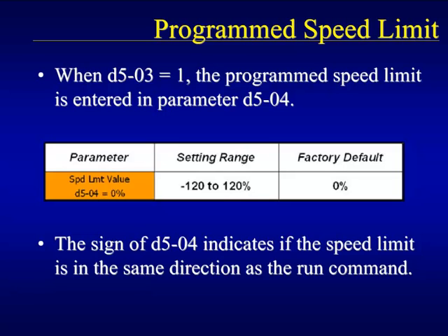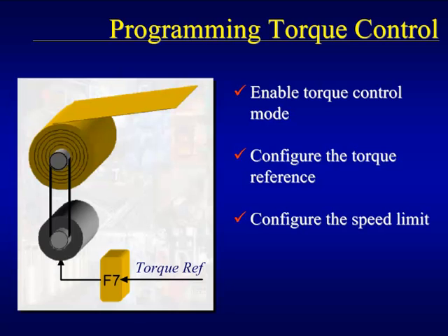Parameter D504 is the value used as the speed limit when parameter D503, speed limit selection, is set to setting 1. The speed limit is programmed in percentage of the maximum frequency set in parameter E104. The polarity of the speed limit is used to indicate the direction of the speed limit. If the speed limit is positive, the speed limit is in the same direction as the run command, and is in the opposite direction of the run command when the speed limit is negative. This completes setting up the speed limit and thus completes programming torque control in the F7.